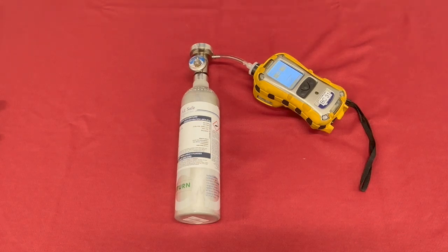Now, this is important because when you're using this meter at a fire scene to measure for hydrogen cyanide, to make sure we can come out of our air packs, you have to slow down. Remember this 240 seconds. When you walk through a building, you need to spend 3 or 4 minutes in each area where you're taking readings to give this hydrogen cyanide sensor time to adjust. If you watch the sensor as it's adjusting, you can see when it finally stops fluctuating a little bit. That lets you know you've reached where it's going to level out. But if you just walk through a building as quick as you can, you'll be taking readings 2 or 3 minutes behind where you're actually standing. So that's an important thing to remember as we're using this meter on a scene.